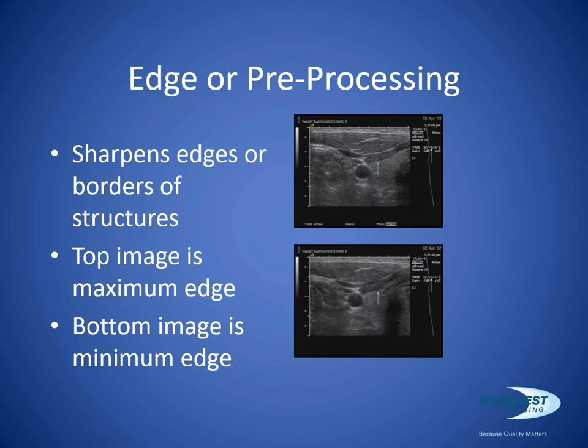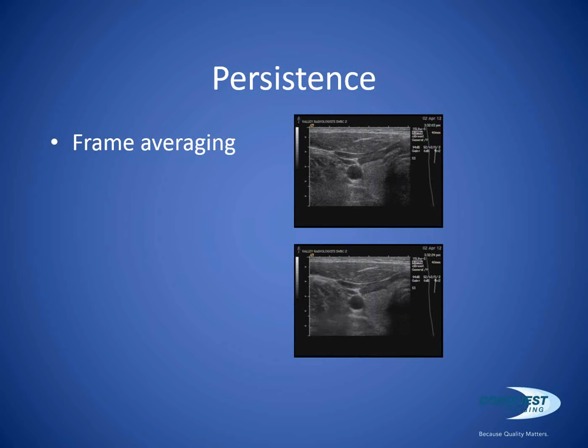Persistence. Persistence is telling the ultrasound system, I want you to average X number of frames. A single ultrasound frame is very noisy, very grainy. Multiple ultrasound frames can get a little bit washed out, but with no frame averaging at all, the image is very unpleasant to look at. And so we want the ultrasound system to average several frames together.